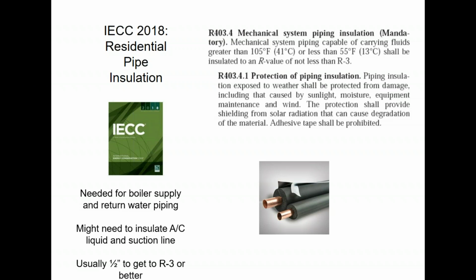So specifically, if you want to make the interpretation, I would say every boiler, both the supply and return piping, needs to be insulated, with perhaps the exception of radiant floor systems, because they might not be above 105 degrees, and they're certainly not below 55. So for radiant floor systems and the distribution piping to those floor systems, you would not have to insulate if you keep it below 105. But all of your regular boiler jobs that are going to radiators, baseboard, air handlers, stuff like that, you probably got above 105 degree supply, so you're going to have to insulate that in those cases.